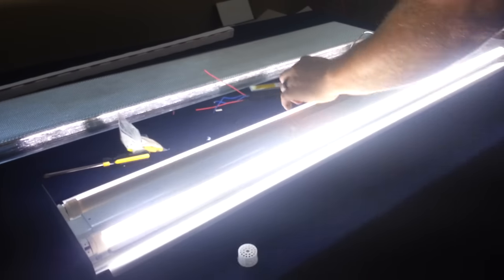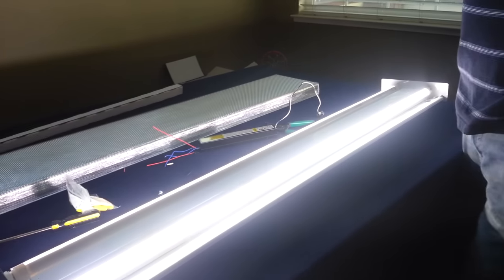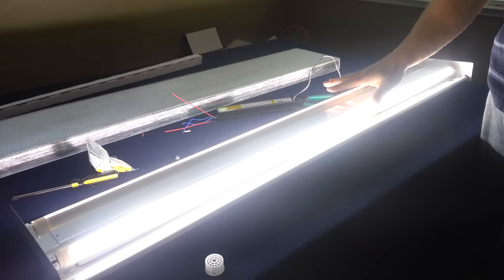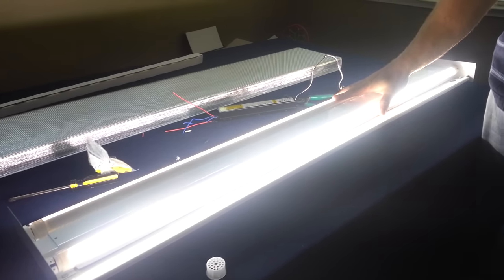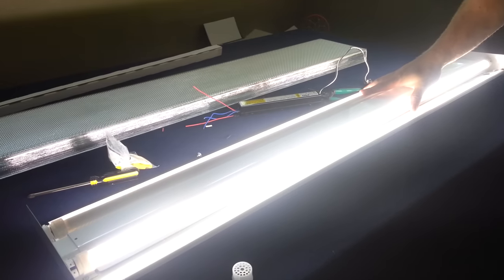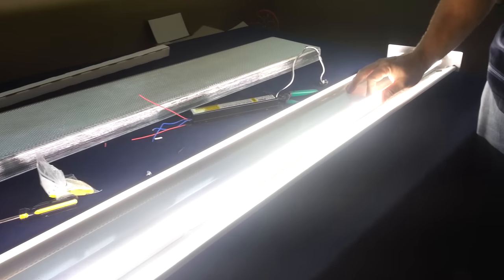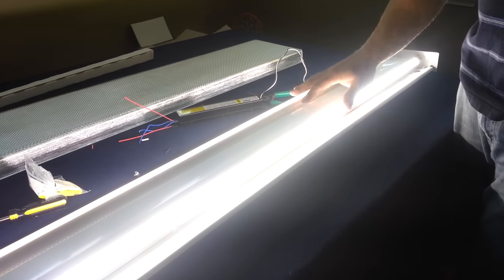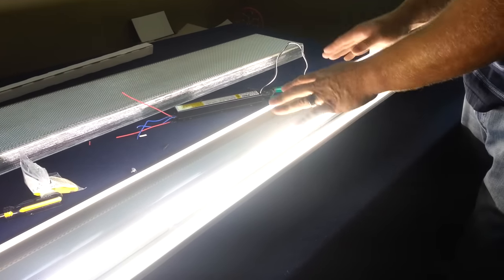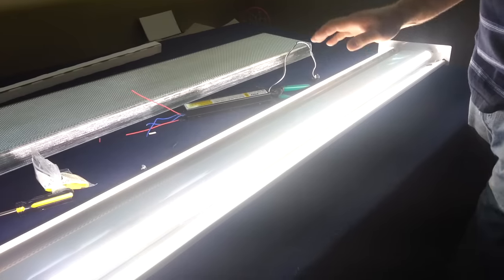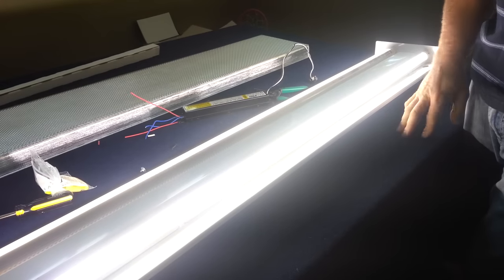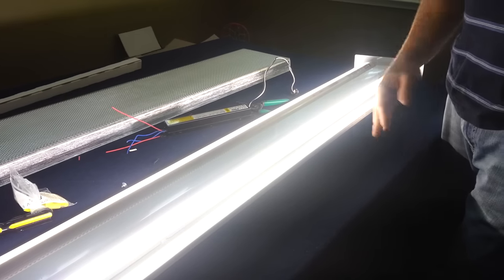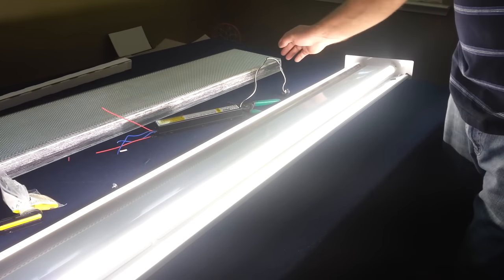If you fail to remove the ballast and you put in the LED lights and you have not removed the ballast, your LED lights will flicker. That's because you have your driver with your ballast. So make sure you bypass that ballast. Very simple, very easy to do.